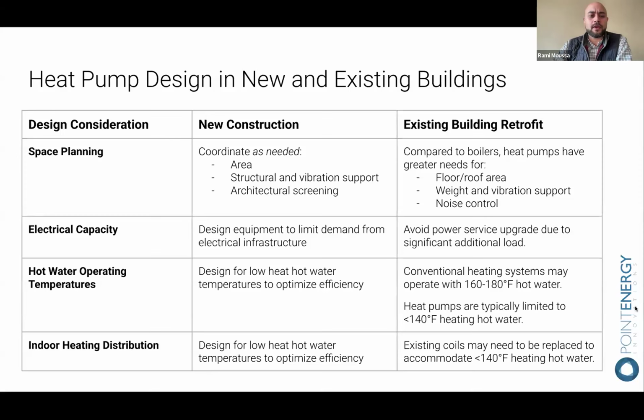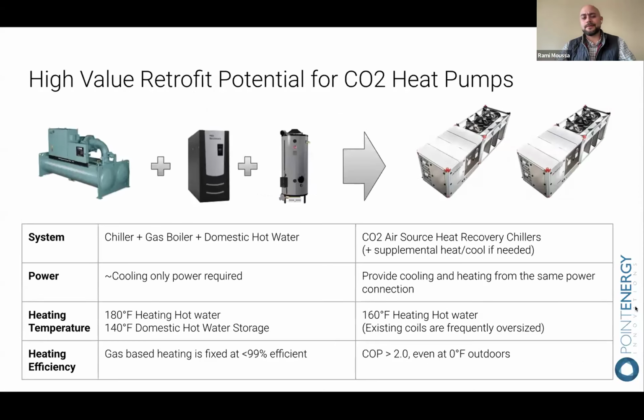Let's review that ideal value trade-off or proposition that the system brings here. If we were to replace an existing system or try to integrate CO₂ heat pumps into a system that uses conventional equipment like chilled water systems, natural gas boilers, and natural gas domestic hot water heating equipment, we could replace that with fewer pieces of equipment. One piece of equipment can serve all three of those duties. And in doing that, we have fewer points of connection for power, as opposed to electrifying the boiler and then electrifying domestic hot water equipment.